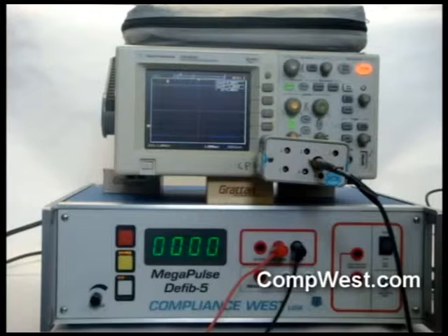it to obtain waveforms. The digital oscilloscope we use is an Agilent DSO3062A, and your scope may have different methods to adjust settings than ours, but the methods we show here can be applied to any digital scope with 60 MHz or better bandwidth. Using a trimmed P6015 with our Agilent DSO3062A, we will describe the method used to capture the voltage waveform for the 100 ohm resistor internal to the Defib 5 to an oscilloscope.